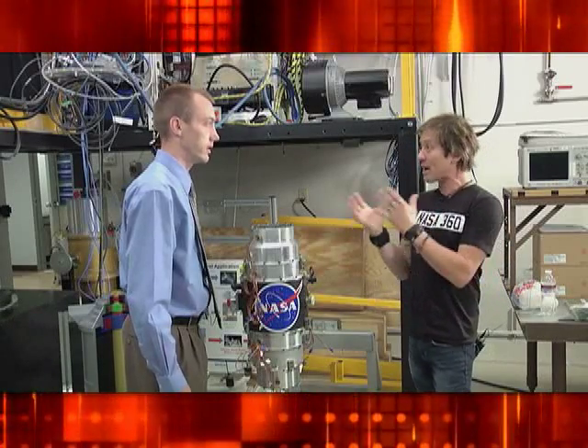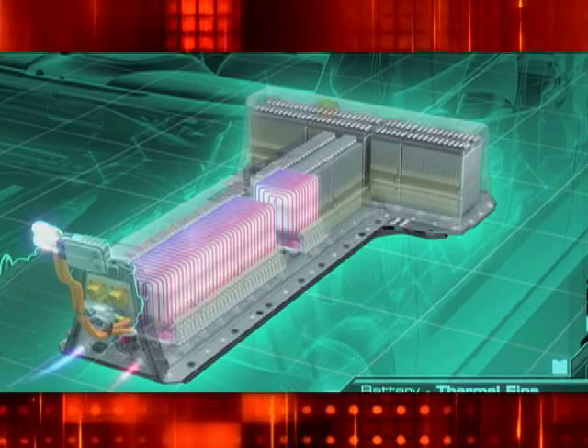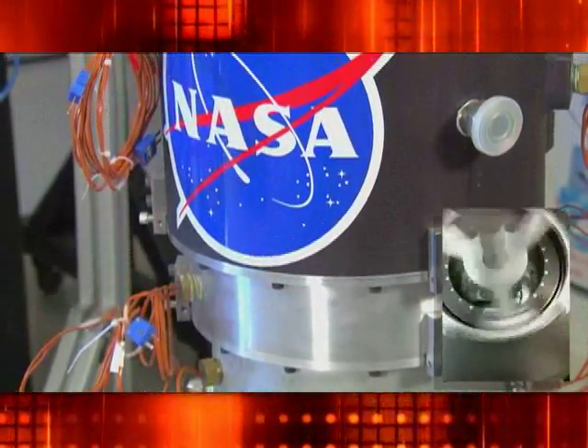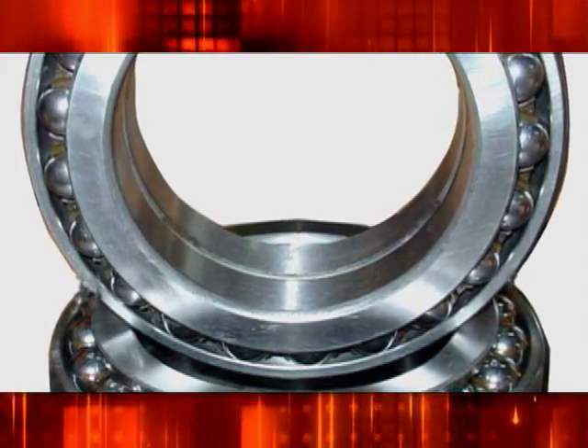We're basically talking about an energy storage device, like a battery. How is this different than chemical batteries? We're fundamentally different in the way we store energy — it's stored mechanically, whereas a battery stores energy using chemical transformations. That's sort of why a battery wears out after a year, two years, or five years. We store energy by what's called kinetic energy in the rotating mass, so we're able to build a system that survives for a lot longer time. We also use magnetic levitation, so there's no friction, no wear.